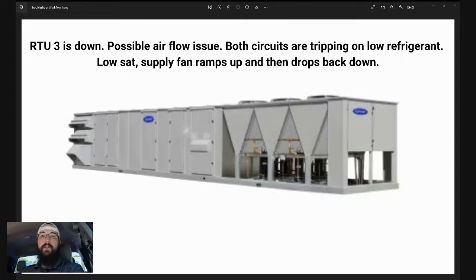Then you could see the other coils in that circuit stay on, while that fan relay wouldn't. That could also be an indicator that we've got a weak transformer. So the transformer can't carry the load like it needs to. Maybe it did at one time, but it's not failed yet, but it's getting weak. And so as it loads up and more coils get put on that transformer, more stuff is applied to it, the voltage begins to drop more and more off of that transformer. And that leads to the weakest coil is going to drop out first.